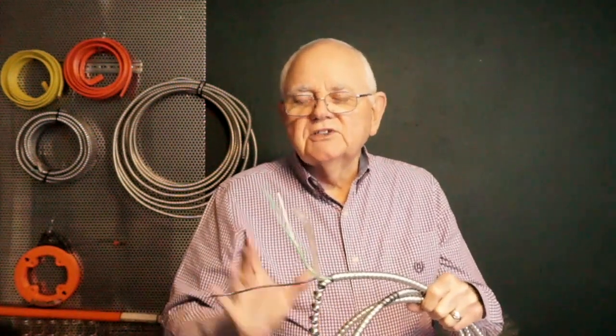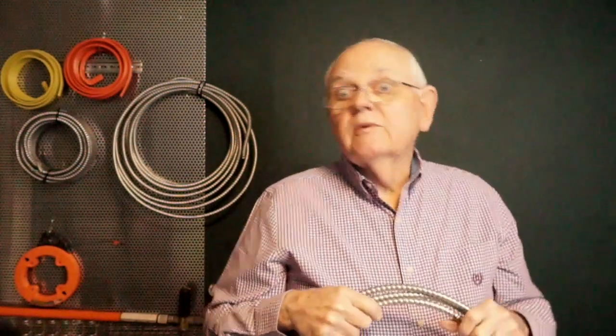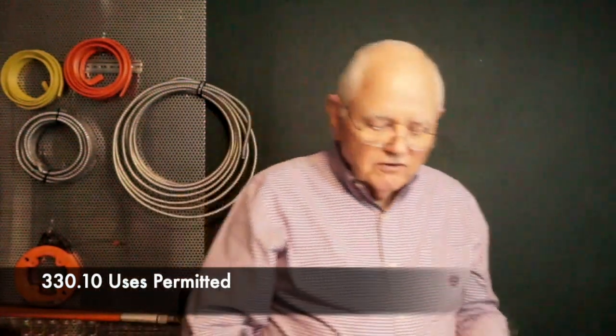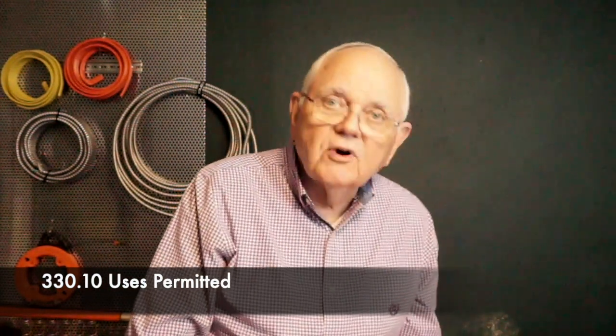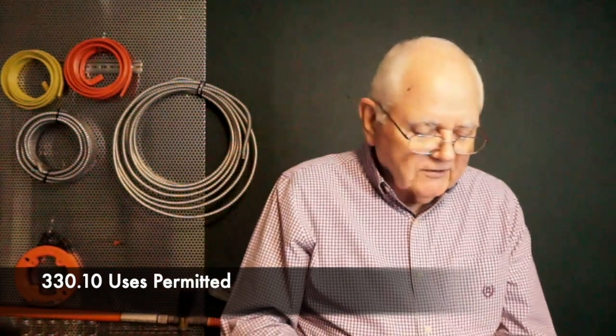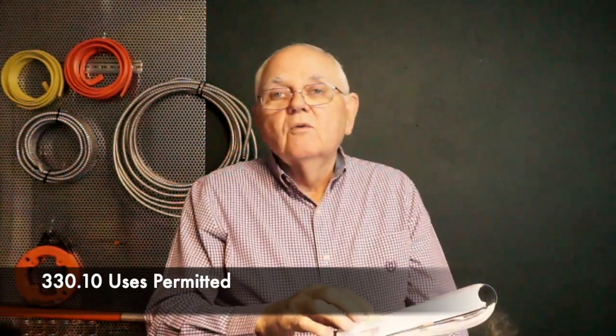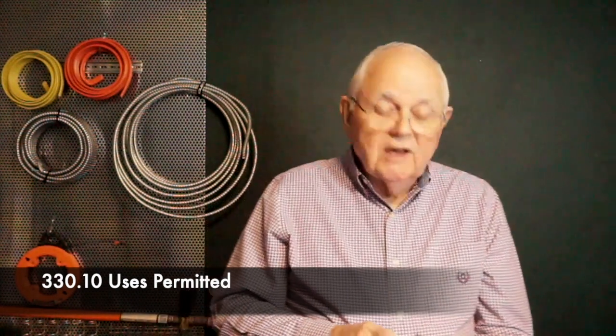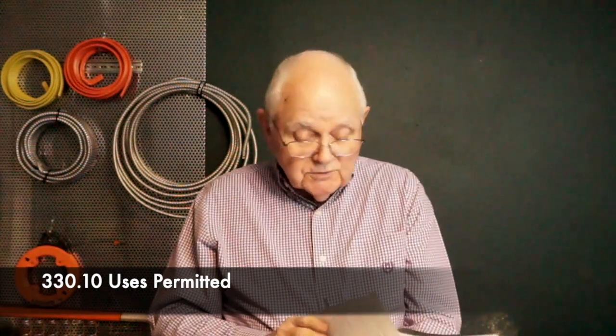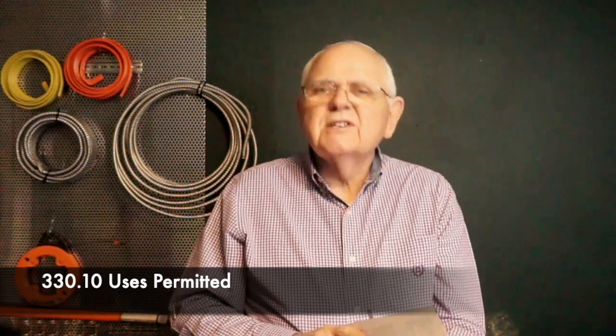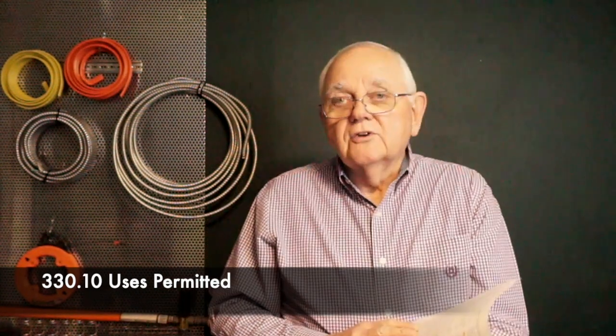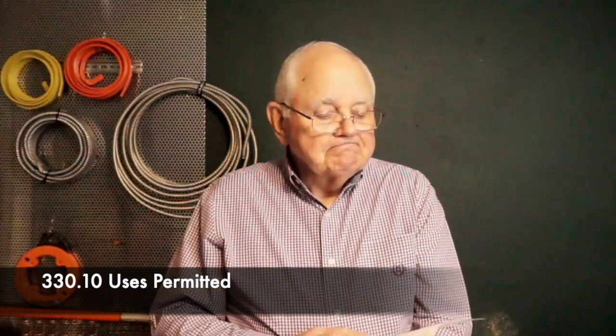It's used as an equipment grounding conductor, where we go to find insulation and ampacity information and so forth. And let's talk about where we can use it, maybe where we can't use it. 330.10, right? We know that .10 is going to cover uses permitted. So let's take a look in the code book, in our 2020 code book, at 330.10, uses permitted. Well, it gives me actually 12 different general use provisions, some specific uses. I can use it in cable tray. I can use it underground if it's identified for that use. I can bury it in concrete if it's identified for use as well.